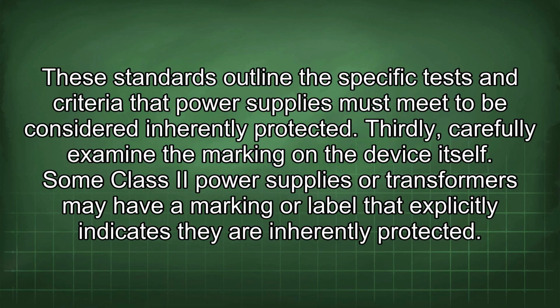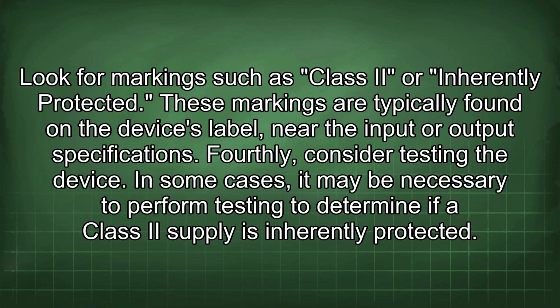Thirdly, carefully examine the marking on the device itself. Some Class Roman II power supplies or transformers may have a marking or label that explicitly indicates they are inherently protected. Look for markings such as Class Roman II or inherently protected. These markings are typically found on the device's label, near the input or output specifications.